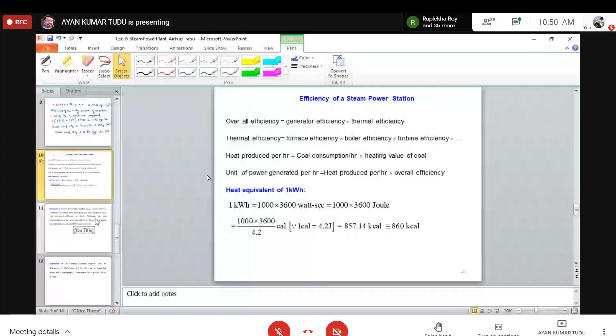As you can see, example 3, a very simple problem: a 100 megawatt steam station uses coal of calorific value 6400 kilocalorie per kg. Thermal efficiency of the station is 30%. Electrical efficiency is 92%. The heat equivalent is also given. We have to find out the coal consumption per hour when the station is delivering its rated full load. So first of all, we know these equations.